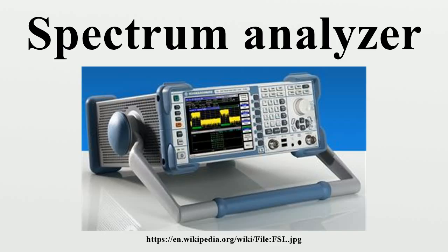In EMC testing, a spectrum analyzer is used for basic pre-compliance testing. However, it cannot be used for full testing and certification. Instead, an EMI receiver is used. A spectrum analyzer is used to determine whether a wireless transmitter is working according to federally defined standards for purity of emissions. Output signals at frequencies other than the intended communications frequency appear as vertical lines on the display.